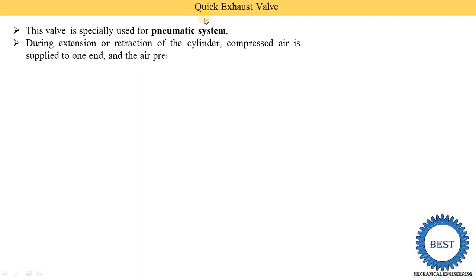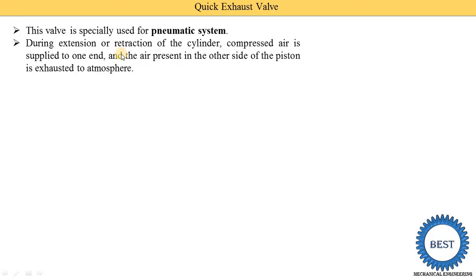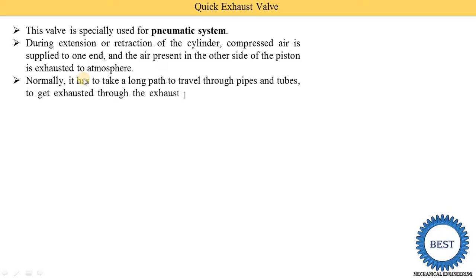The quick exhaust valve is used for the quick removal of air. During extension or retraction of a cylinder, compressed air is supplied to one end. During extension stroke, compressed air is supplied to the cap end side, and at the same time on the rod side the air is exhausted to the atmosphere. Normally the air has to travel a long path through pipes and tubes to get exhausted through the exhaust port of the directional control valve.